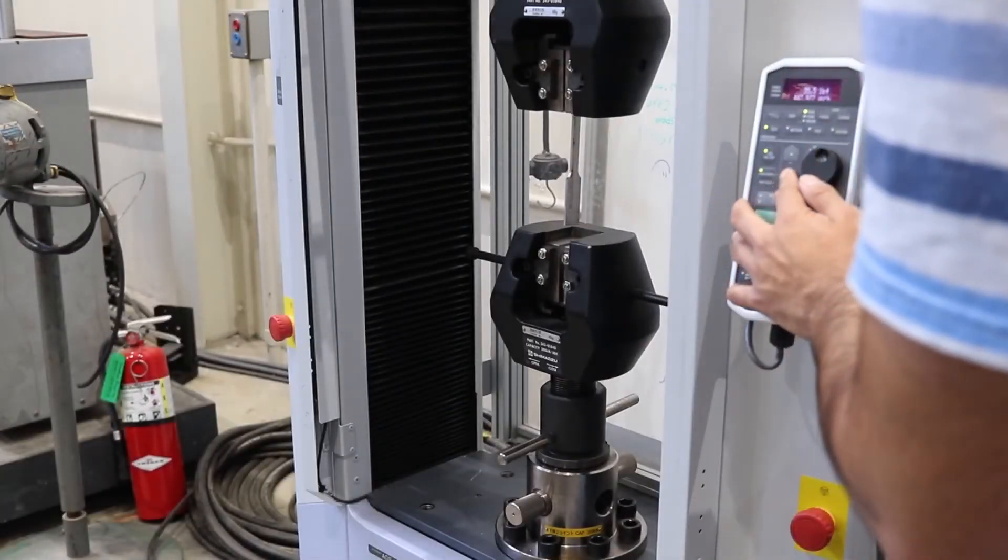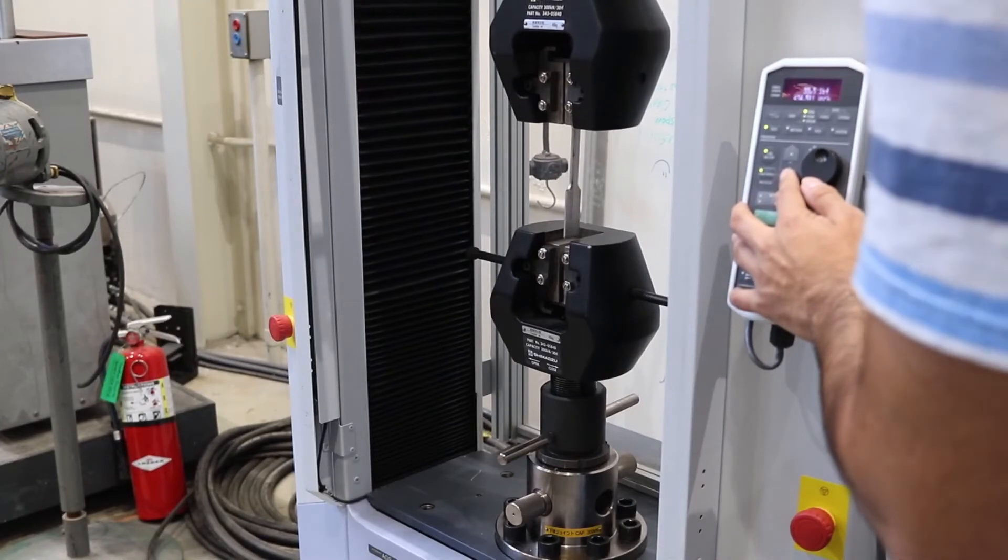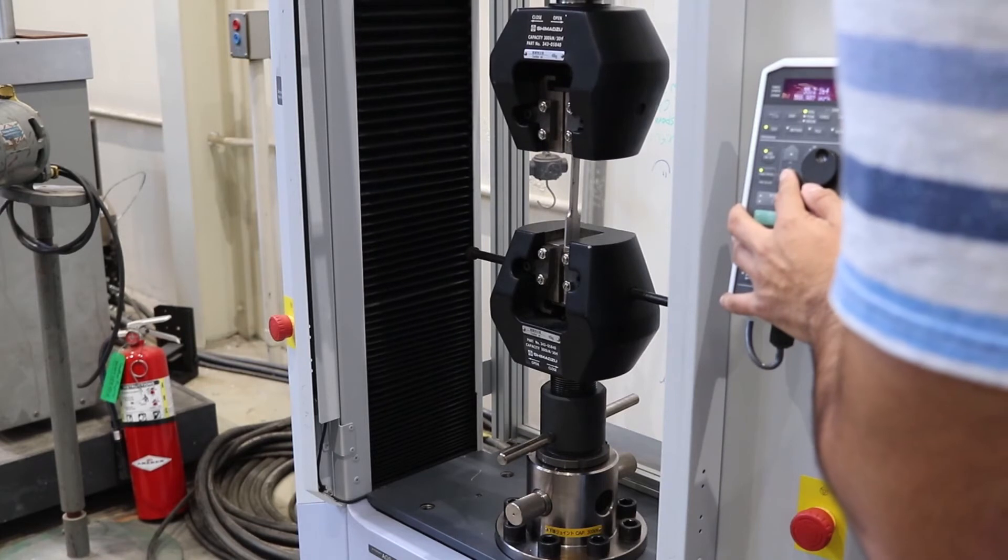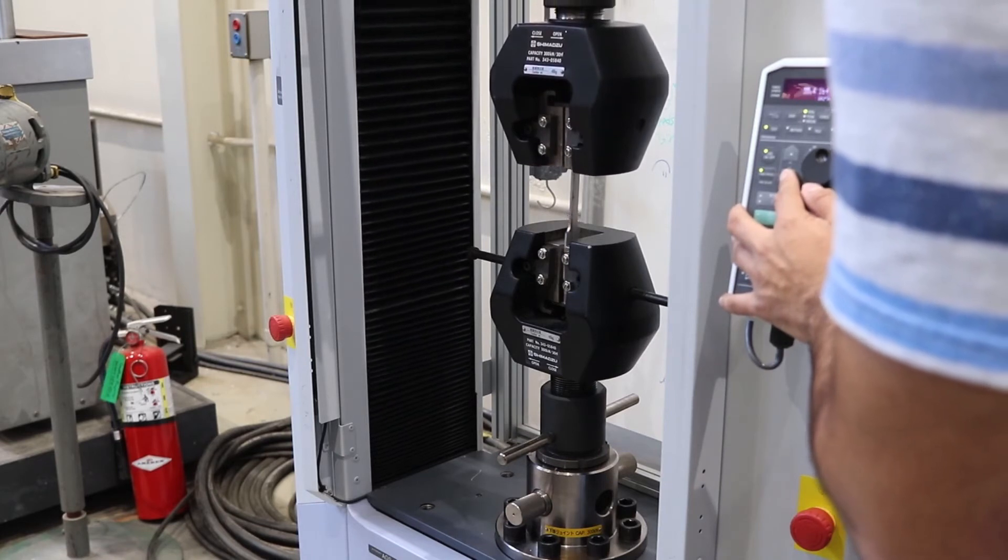Now that the upper jaw is secure, we need to jog the machine down so we can secure the lower jaw. To do so, we click Jog On Off, High Speed, and press the Down button. Again, the specimen should align with the scribe in the face of the jaw.